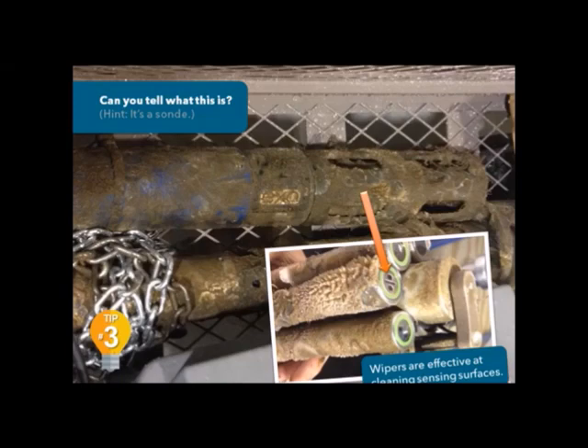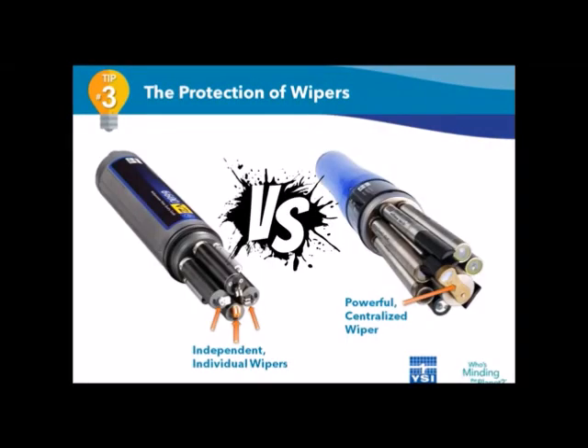So I would suggest that the number 1 accessory to mitigate fouling would be a mechanical wiper or wiping system. For those of you that may not know, a wiper is a mechanism that sweeps over the sensor's surface. In our older sonde platforms, each optical sensor had its own wiper that had a soft pad to sweep across this area. However, in our newer sonde technology, we use a centralized wiper with more torque and stronger bristles to clean a whole suite of sensors simultaneously. This wiping design is more robust because it offers a more thorough cleaning, and there's only a single brush to maintain.